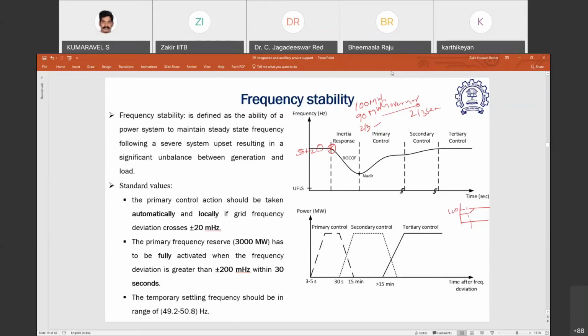What will happen here? Because of the loss of the generation of 800 megawatt in this particular case, this is an electrical circuit. At the end, you have to see the grid as an electrical circuit. It has different generators connected in parallel, and it has a load. Let us say now we are representing the entire load as an aggregate load. Load is constant here in this particular case, and we lost one generation. Let us say it was supplying I1, this was supplying I2, this was supplying I3. So we lost this I2.